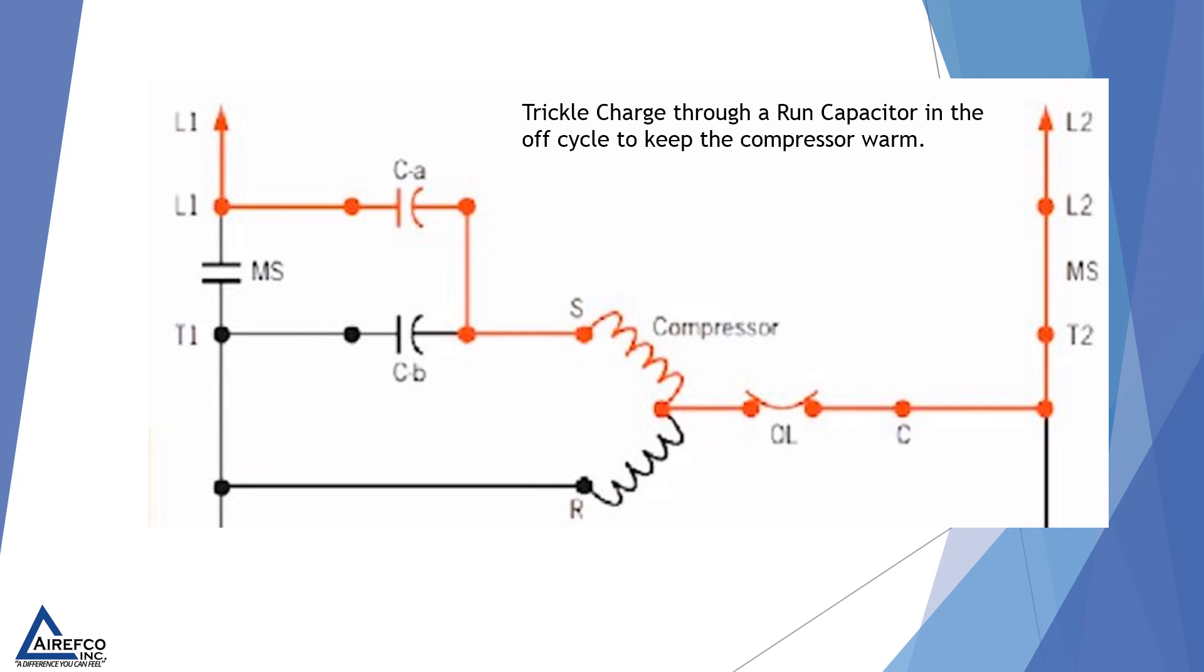One of the ways manufacturers applied crankcase heat in some older units was through a run capacitor. A trickle charge was run through a run capacitor in the off cycle to keep the compressor warm.